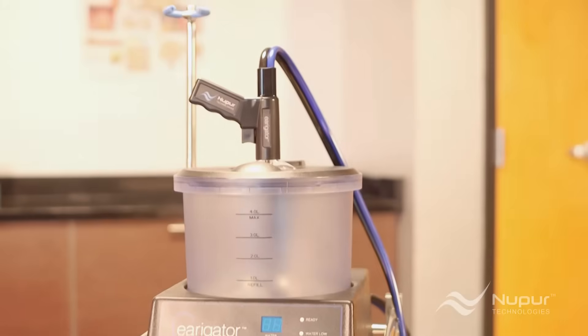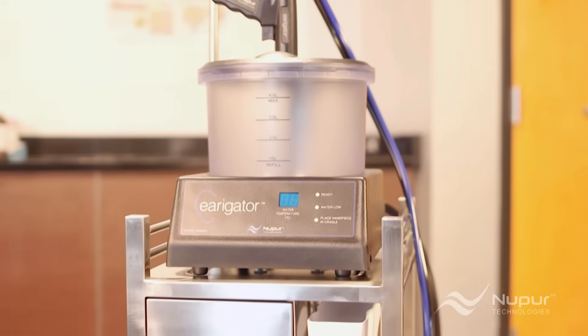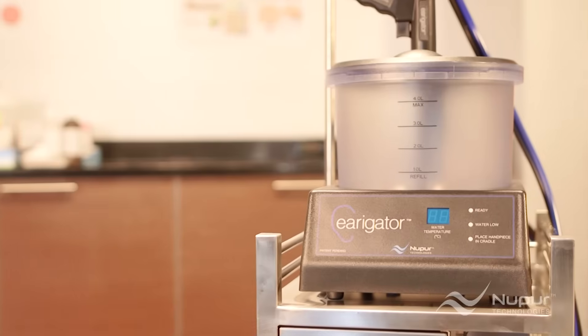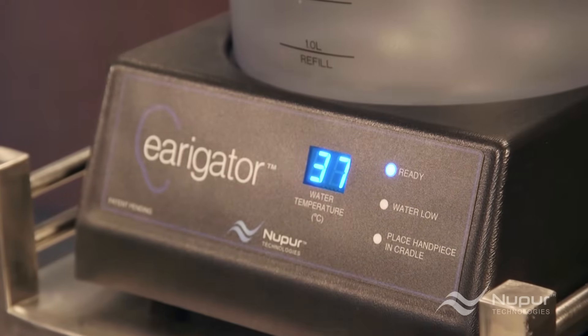If you answered yes to any of these questions, then the Earigator Cerumen Management System by Nupur Technologies is your solution. Designed by an ear, nose, and throat doctor, the Earigator is a self-contained irrigation unit that heats water to body temperature, avoiding any caloric or vertigo effects, while giving you the ability to control flow and pressure within a safe limit.